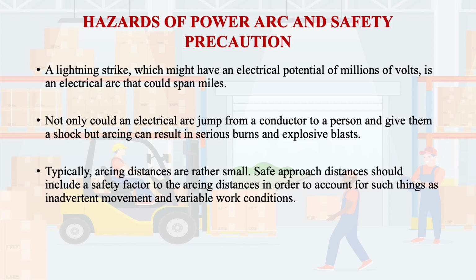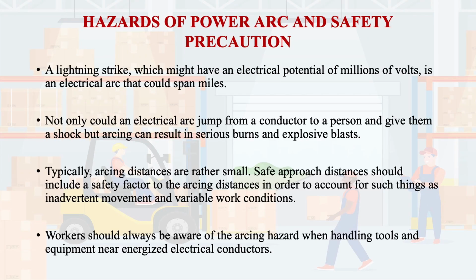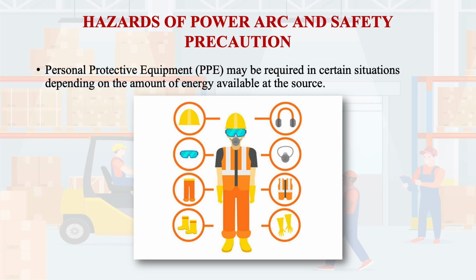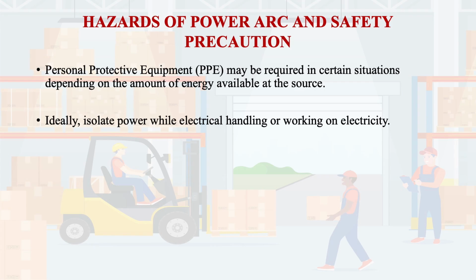Typically, arcing distances are rather small. Safe approach distance should include a safety factor added to the arcing distance in order to account for things such as inadvertent movement and variable work conditions. Therefore, safety distance cannot be constant. As such, it is always advised to have a factor of safety of at least 2 times the actual safe distance. Workers should always be aware of the arcing hazard when handling tools and equipment near energized electrical conductors. Personal protective equipment (PPE) may be required in certain situations depending on the amount of energy available at the source. Ideally, isolate power while handling or working on electricity. Thanks for learning safety skills.